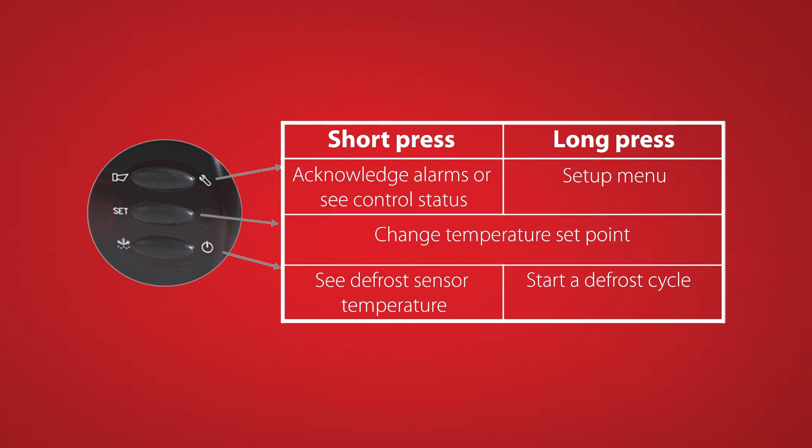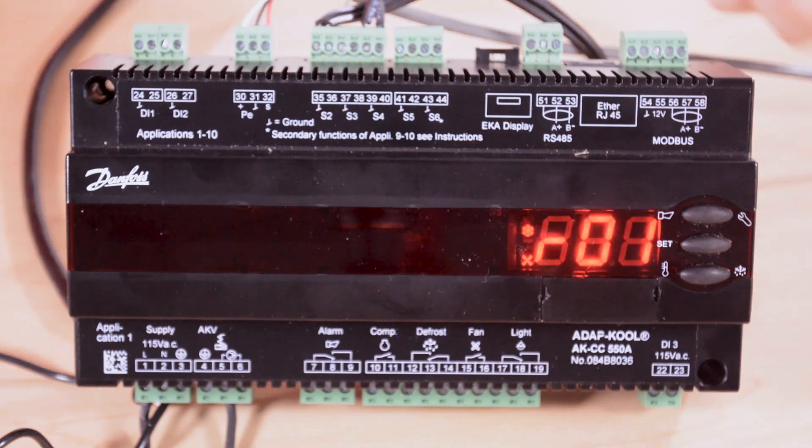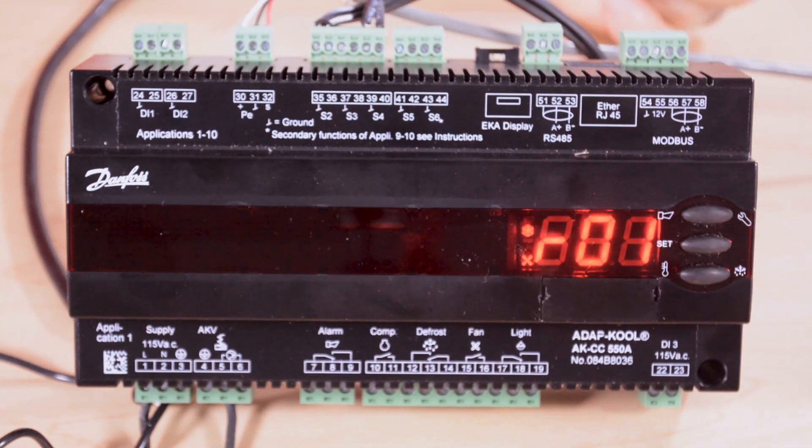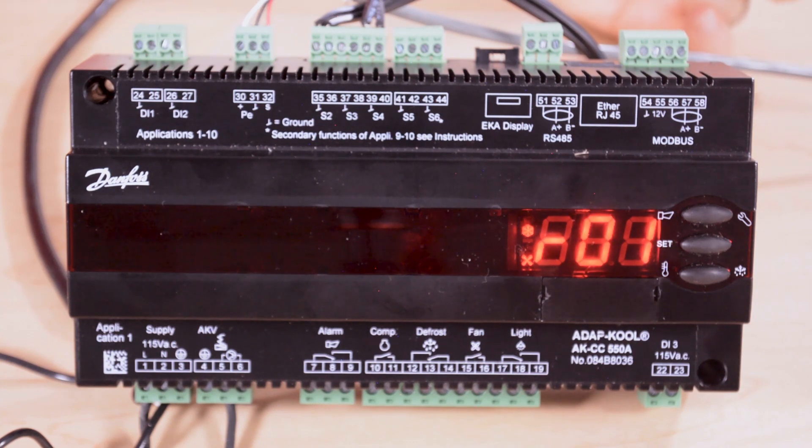If we press this top button longer we can enter the parameter list. The parameter list will give us all the programming options for the controller starting with R01. If we don't press any buttons for 15 seconds the controller will time out and go back to the temperature display.